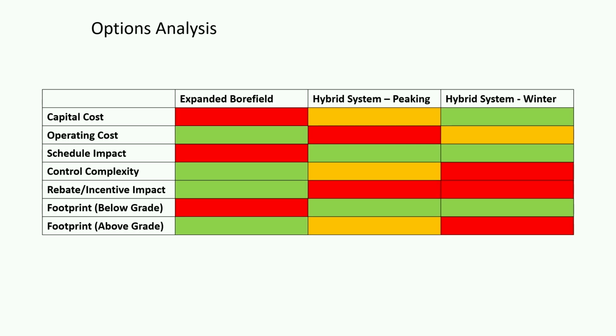So just in summary, comparing all of our 3 options, your experience is going to vary with all of these. This is a very general rule, and different solutions work for different clients. So obviously, the first one, capital cost. Drilling a borehole is really expensive. If you find that in order to keep your thermal drift under control you're going to need to drill a lot more boreholes, you may have a situation where it's going to be cheaper up front to install one of these chillers, install one of these dry coolers, or some type of hybrid system to keep your system in check.